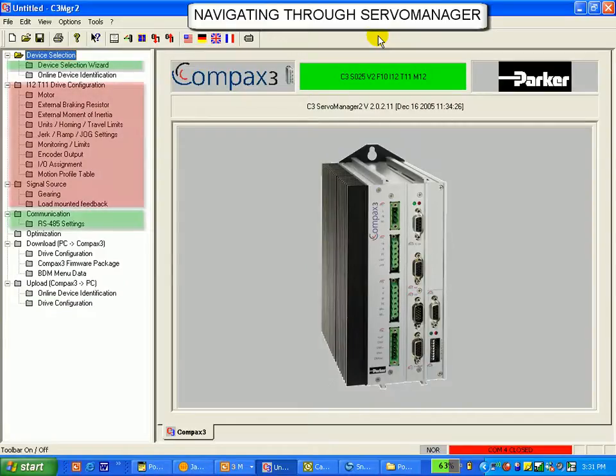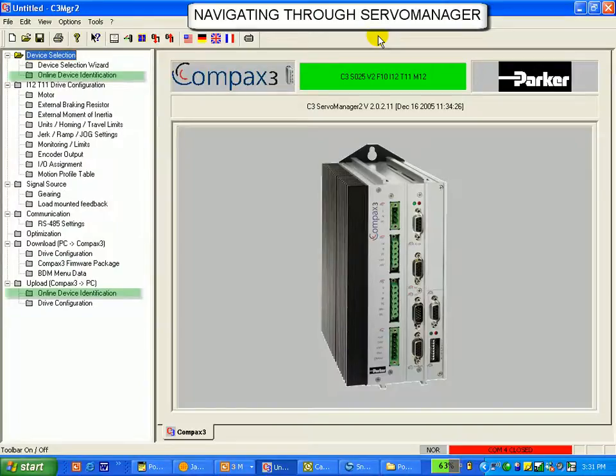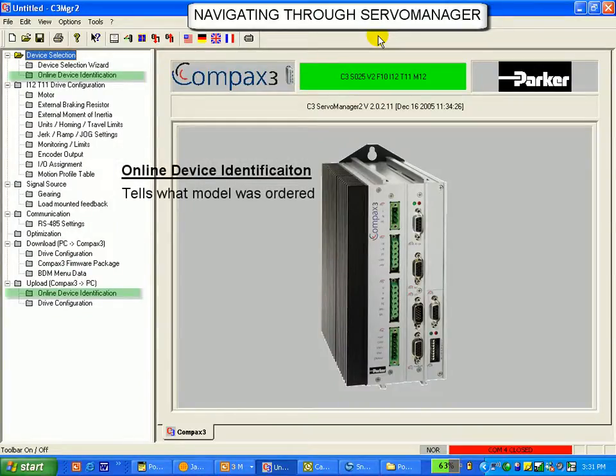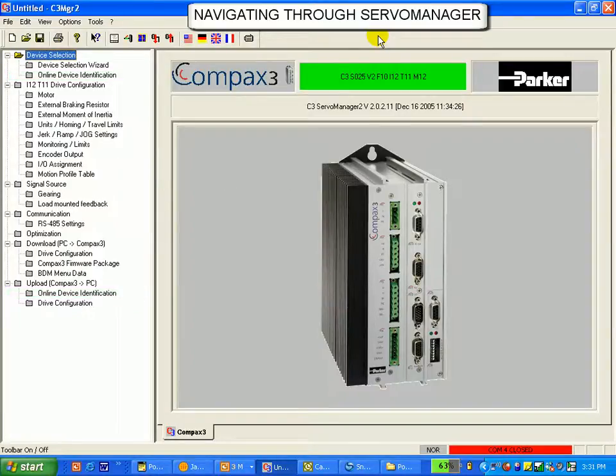The navigation tree also allows you to set up RS-485 communications, launch the optimization window for diagnostics and commissioning aids, download the complete drive configuration and firmware to the Compax 3, and upload the complete configuration from the Compax 3. One other tool here is the online device identification. This will essentially ask the drive what model the factory built it to and tell you what drive you have it set up as. The Compax 3 allows you to dumb the drive down, so it will list these two types among other valuable information.